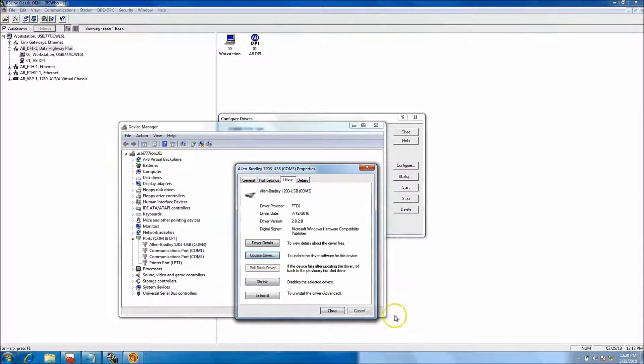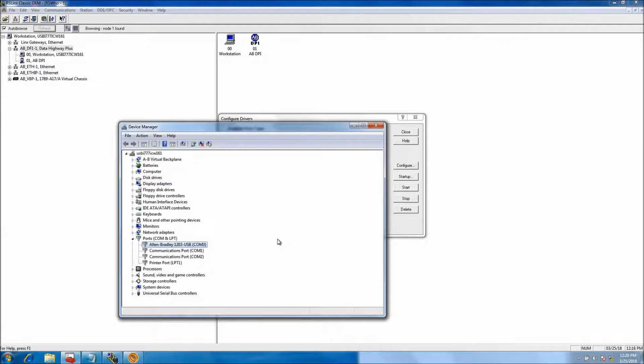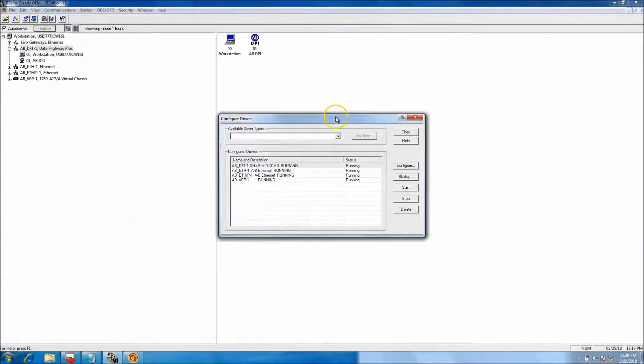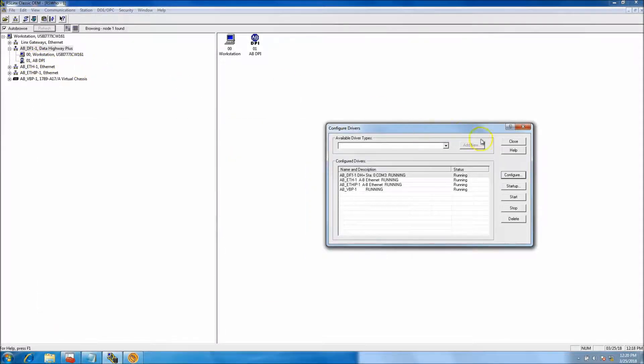It's most likely going to point to the device automatically. The first time you plug it in it should load the driver. If by chance it doesn't, right-click — if there's a caution symbol, try to scan for the device. Those are common things you'll see when setting this up. Device Manager is very important to using the 1203 USB, so make sure you know what COM port you're at and how you're set up. If it's not set up properly, you won't see it in RSLinx.